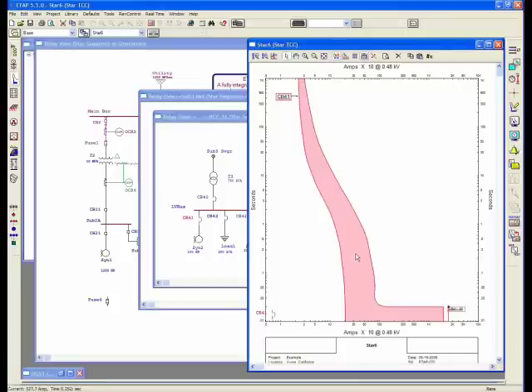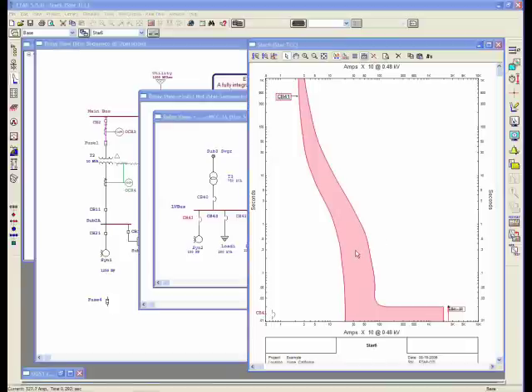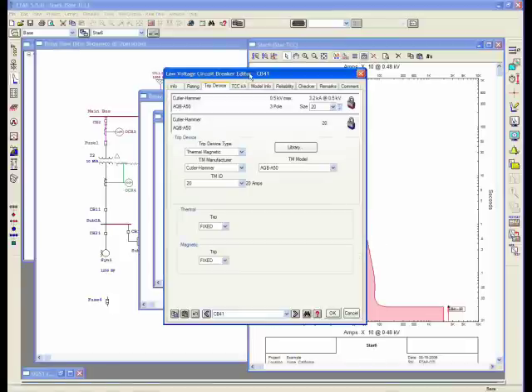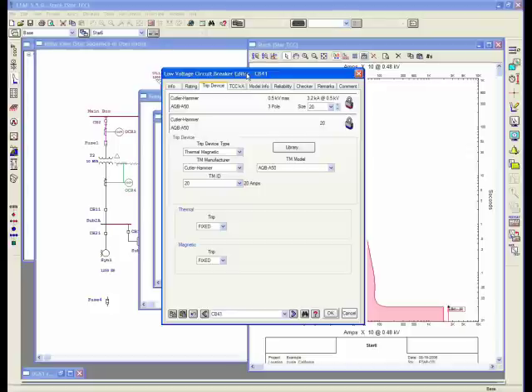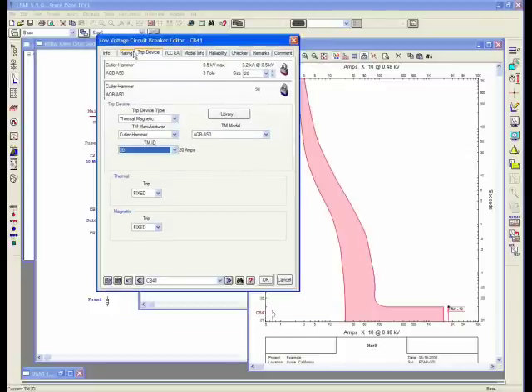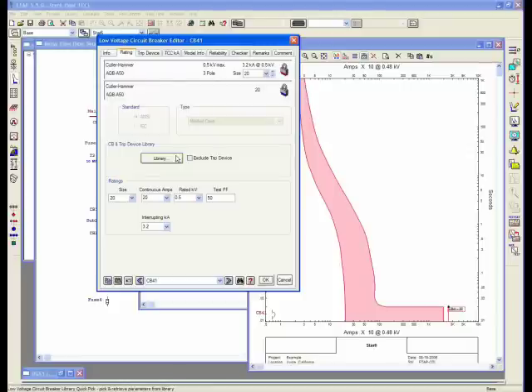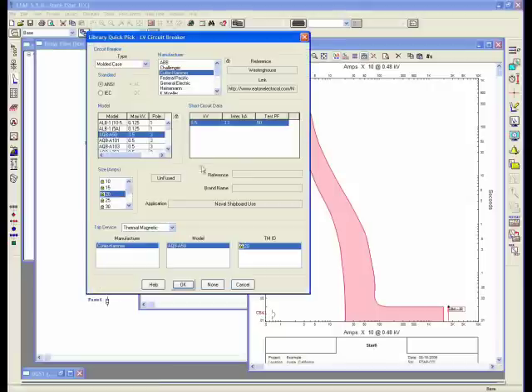Our program is designed so the libraries are valid and verified. What you see on the one line is exactly what the manufacturer provides. We have a very strict, of course, being a nuclear-grade program, all the program is valid and verified. The TCC curves we provide are the manufacturer-published curves, and our deviation levels are 0% for rating and less than 0.1% for most of the other devices for TCC curve points.